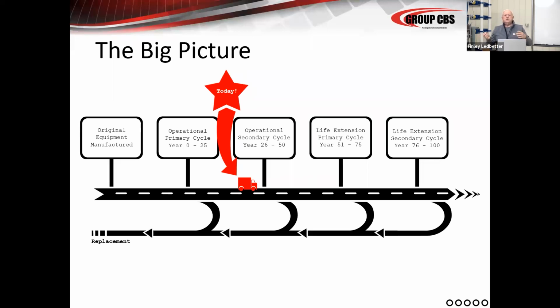When GE, bless their heart, even though they're gone today, hello to all my ABB friends out there, came around and pitched this, when Westinghouse came around and pitched this, when Allis-Chalmers, Brown Boveri, all these people came around and pitched this years ago, basically, they promised us a 20 to 25 year life cycle on this switchgear, and it's done a great job. It's far exceeded that. It has twice exceeded what it was designed to do. And then you see the secondary cycle, which is another 26 to 50 years. And that's where we're at today with most gear. Most gear is over 25 years old, somewhere between 25 and 50 years old.